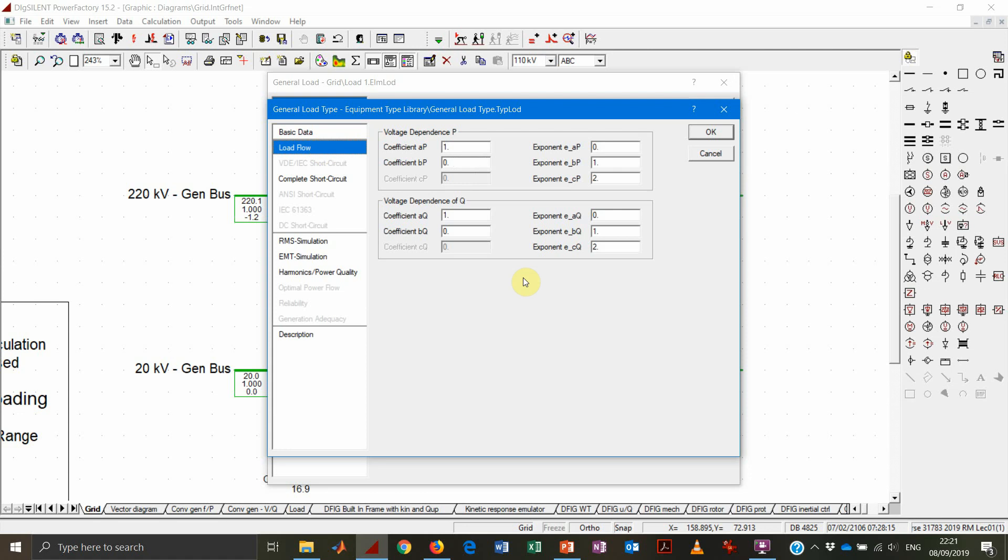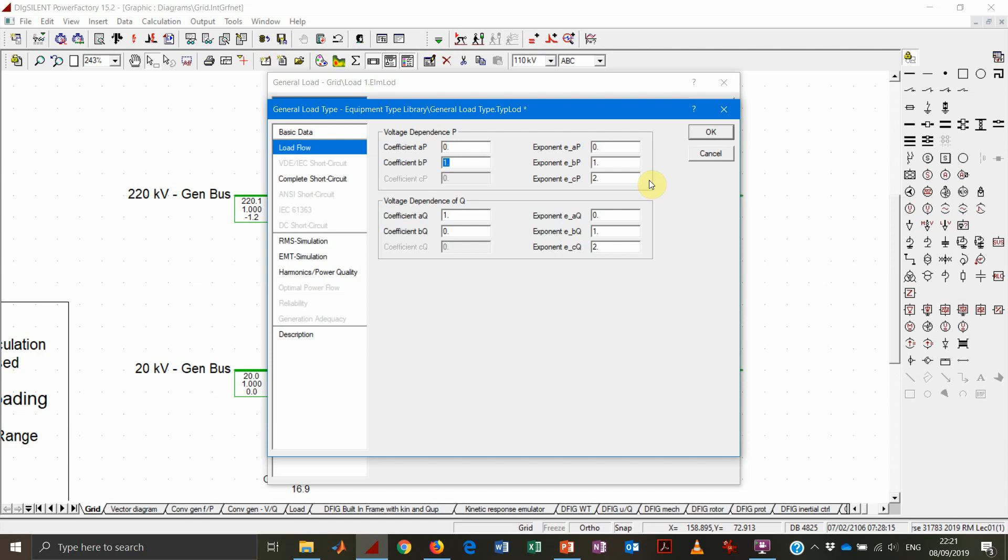And then under the load flow tab, you can find the voltage dependency factor for active and reactive power. So whether the load should be 100% with no dependency on the voltage, 100% on the voltage, or 100% with a quadratic dependency on the voltage. Of course, the same applies for the reactive power.